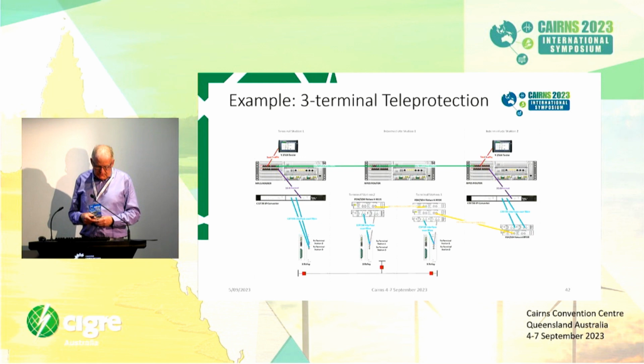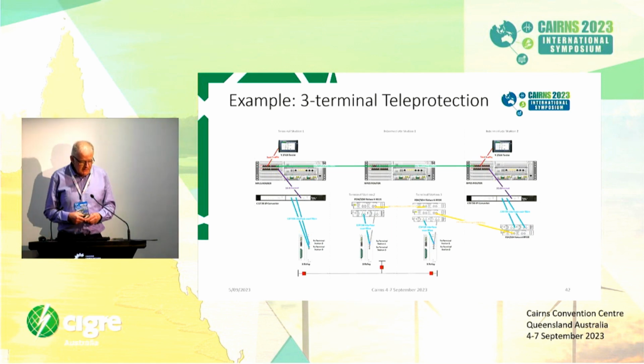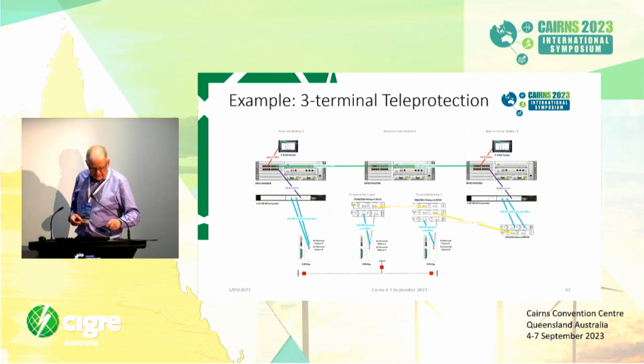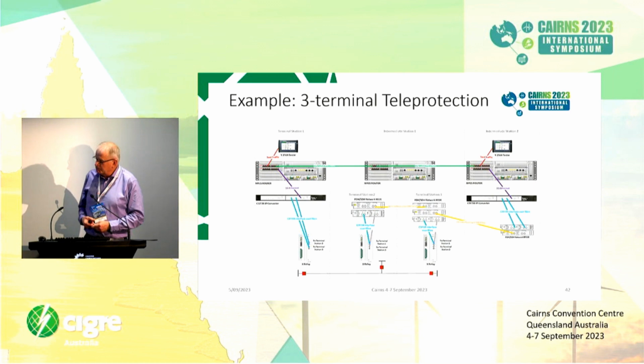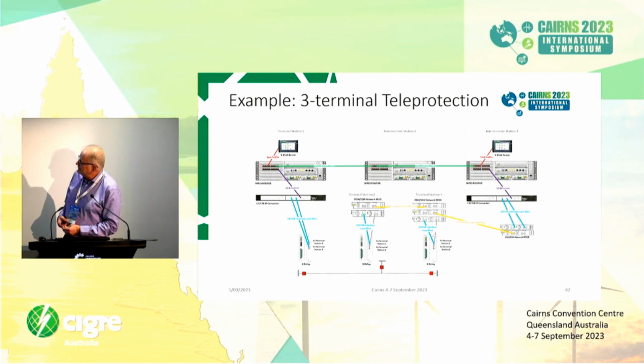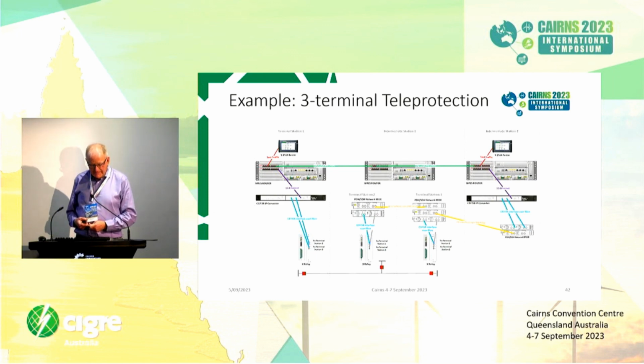At terminal station 1, the protection connects into a C37.94 to IP converter, and then into an MPLS router. You can also see there we've got our Y.1564 tester connected into the router. Then we go via a couple of intermediate substations. When we get to intermediate station 2, the MPLS network then hands off onto a TDM network. So we come out of our router into a C37.94 to IP converter, back into C37.94, and then into a TDM, a PDH network multiplexer. Then we go across to terminal station 3 and then back to terminal station 2 via the PDH network. And that then supplies C37.94 to the protection system.